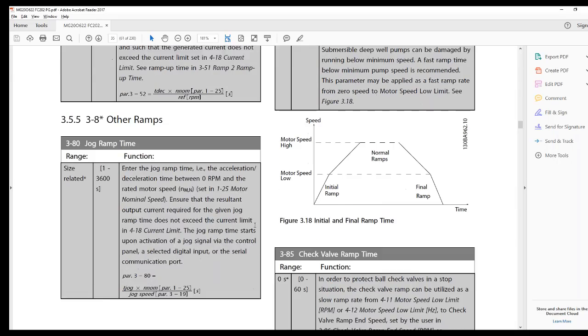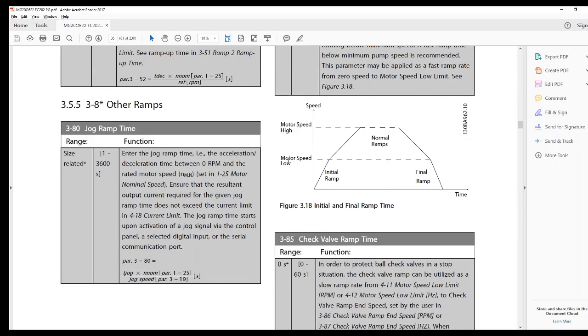But let's say in derag, as I say, we need this kind of profile for starting it. So there's a minimum motor speed, but certain pumps need to get up to speed quick, and then you can take care of the application part of ramping up. So we have the maximum. So if I was deragging after this is set up, it will still do this for starting and getting up to speed. So my preset speed right now is say in this level, but my derag is down here. Every time it starts, it will still go zip and then ramp to the deragging speed, and same with stopping. So it follows the ramp times that are set for basic function of the pump.